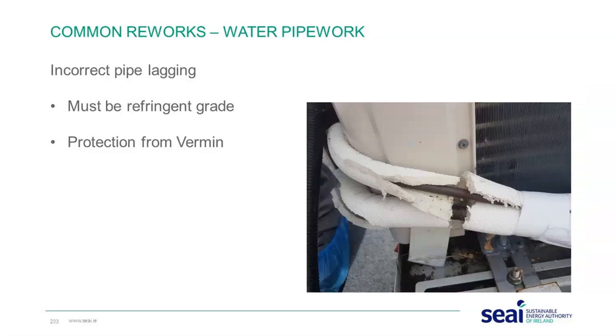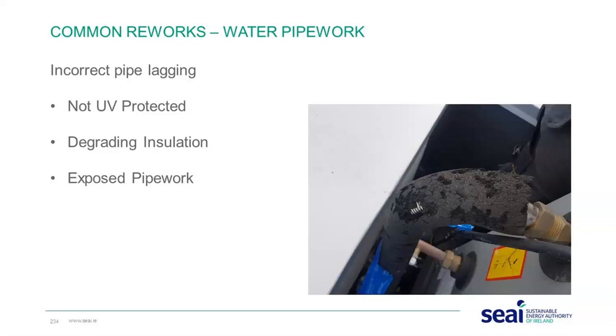Pipe lagging. Quality pipe lagging is important. This is about energy efficiency, and we're trying to distribute the heat from the outdoor unit to the indoor unit. If there's poor pipe lagging, a significant amount of heat is going to be lost before it gets to the useful space. We should also be looking at the durability of the pipe lagging, taking into consideration protecting it from vermin. Just to give an example, as I mentioned earlier, with our inspectors it's probably a month and a half from the time an inspection is done.